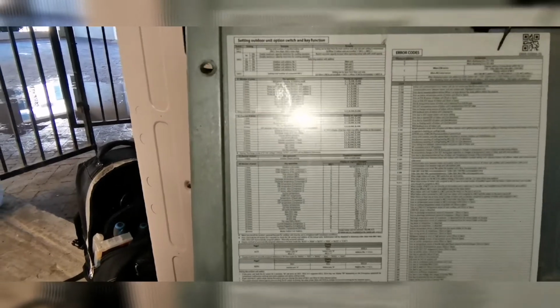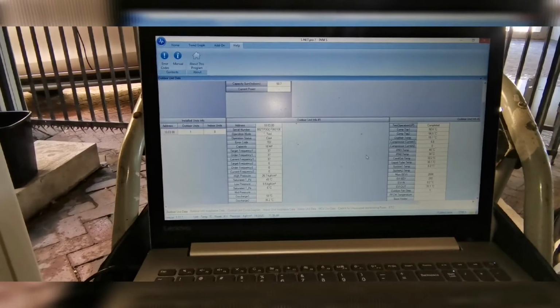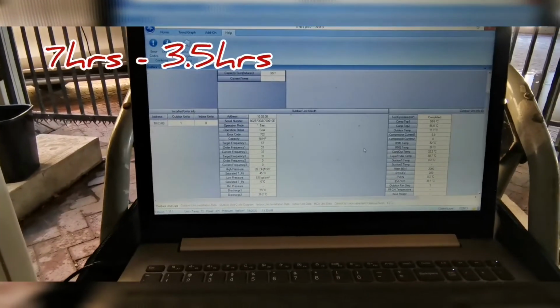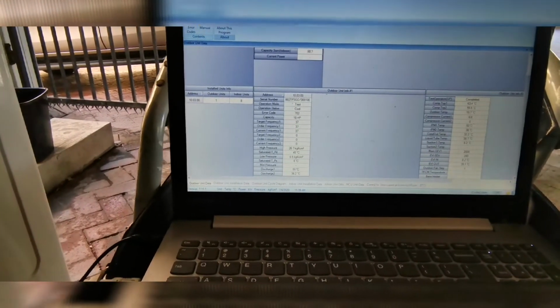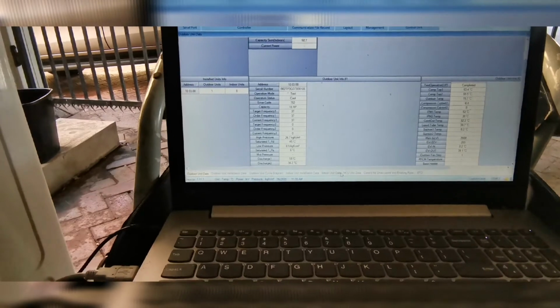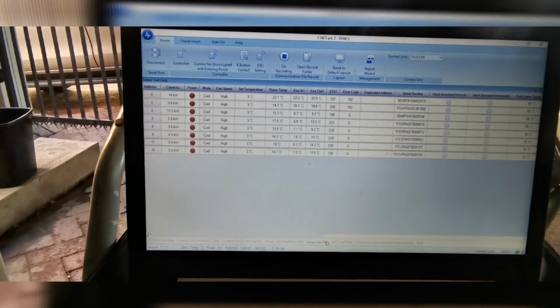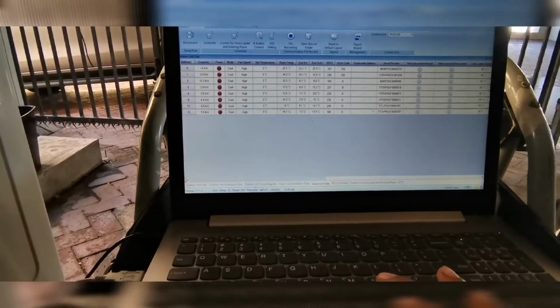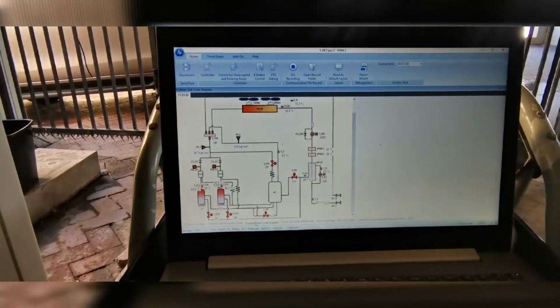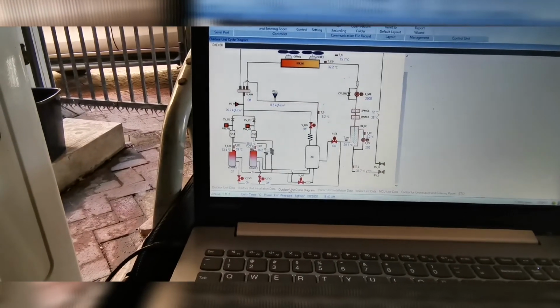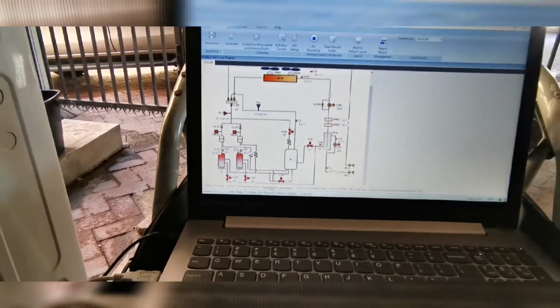As well, if you're working on the outdoor unit, all those error codes are listed over here, which I think is quite convenient, along with a bunch of other functions. Like you saw, we put the system in vacuum mode, and one of the other things that we'll more than likely do is change the oil return cycle. We'll probably reduce that to half. So yeah, I think that's pretty handy. So all in all, everything is looking fantastic. Things are looking great, and I think we're about ready to have a look at the heating cycle, make sure that everything's functioning correctly. But so far everything's looking great, so yeah.